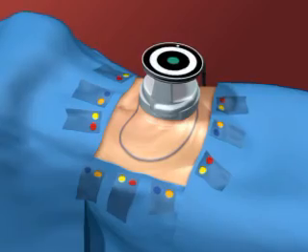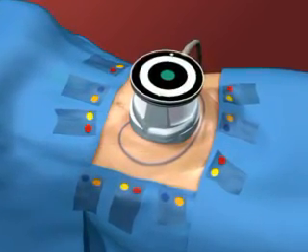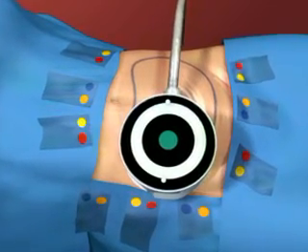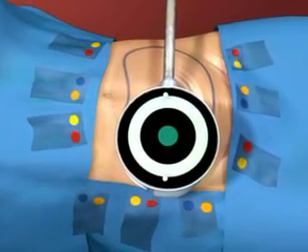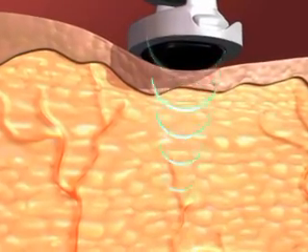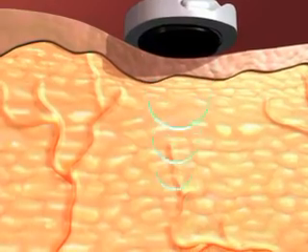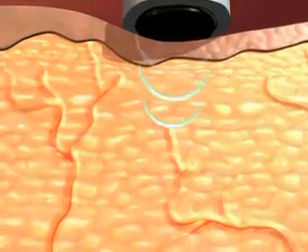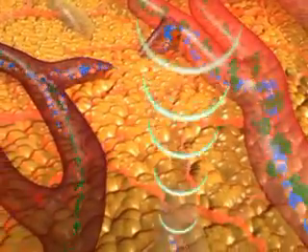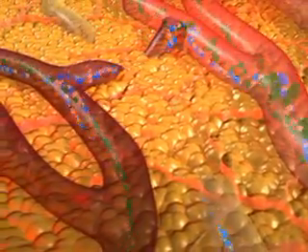The transducer delivers an ultrasonic beam and provides real-time acoustic and optical feedback on treatment. It uses multi-directional acoustic waves to ensure that focused energy is applied to the selected area only. Specific ultrasound parameters of pulse length and energy level ensure selective damage to fat cells only. Non-adipose tissue, not being susceptible to these parameters, remains untouched and undamaged. Built-in controls verify acoustic contact and monitor transducer temperature during treatment.